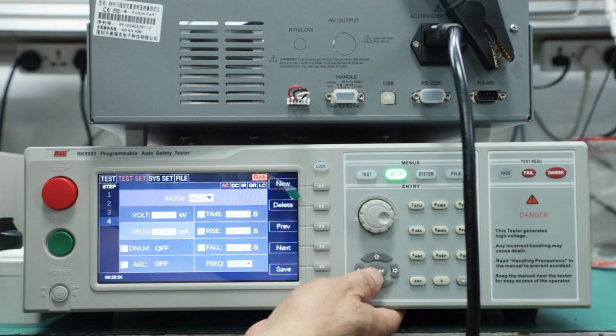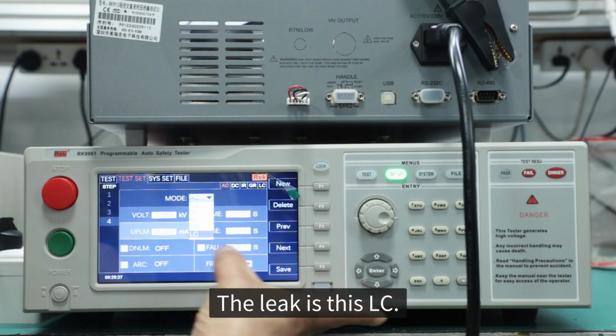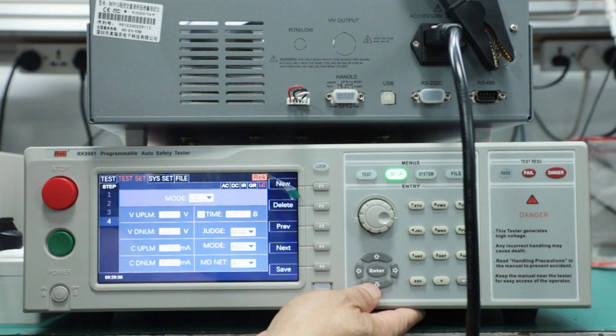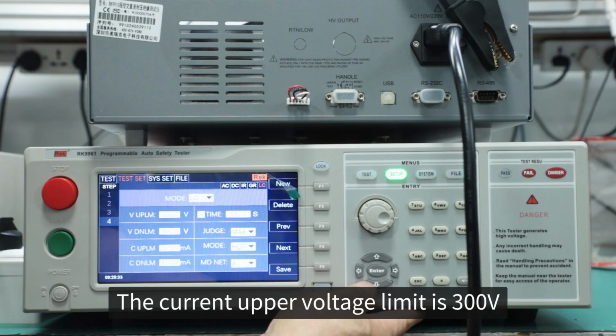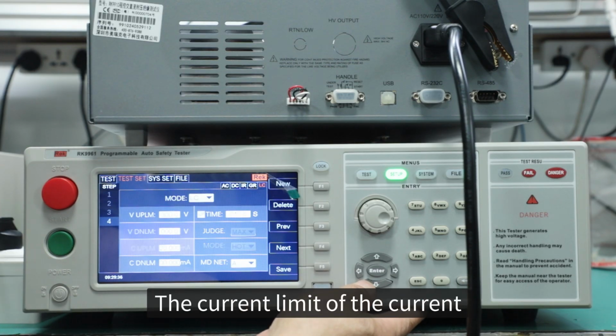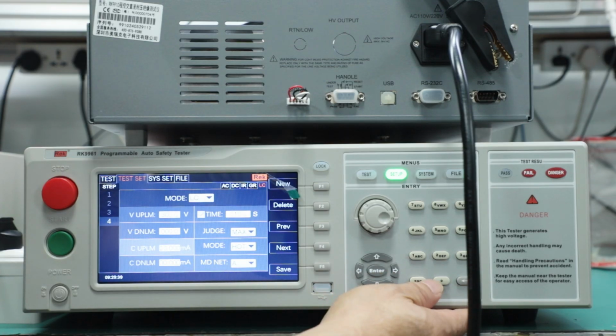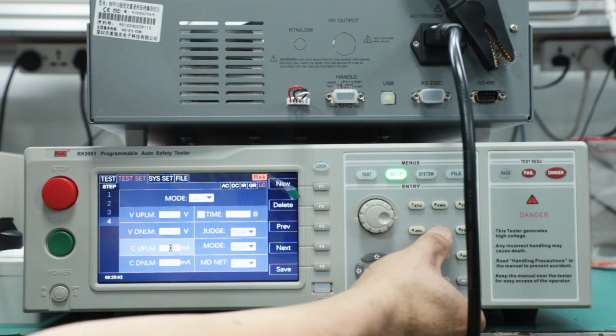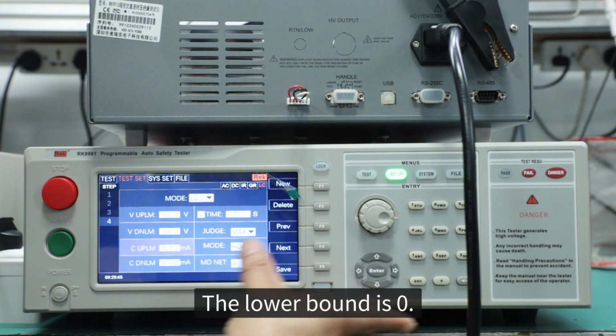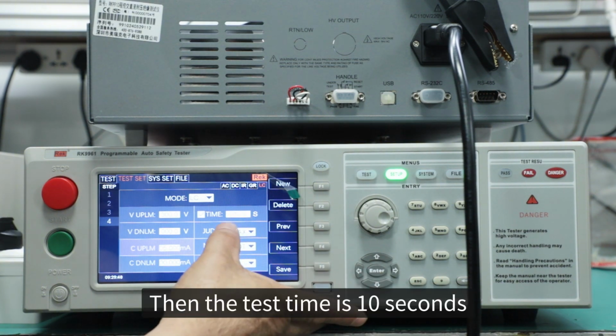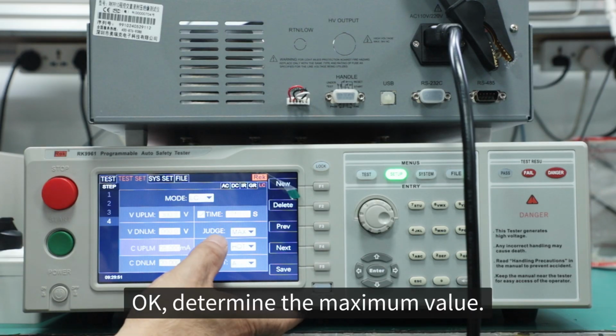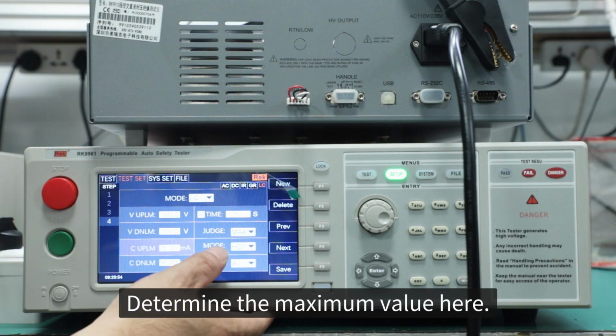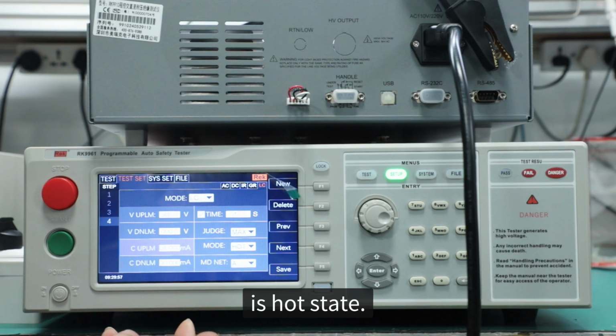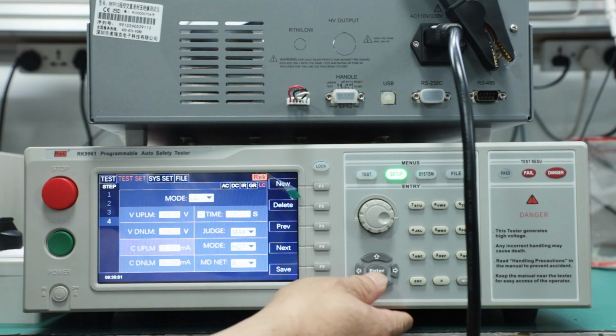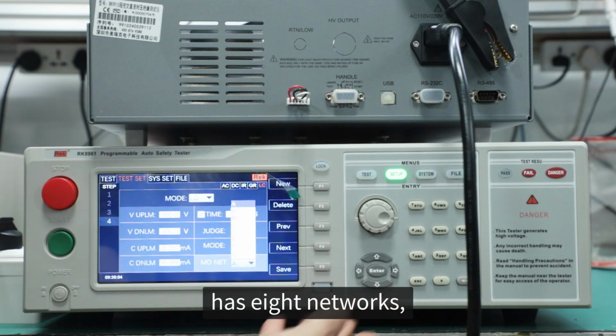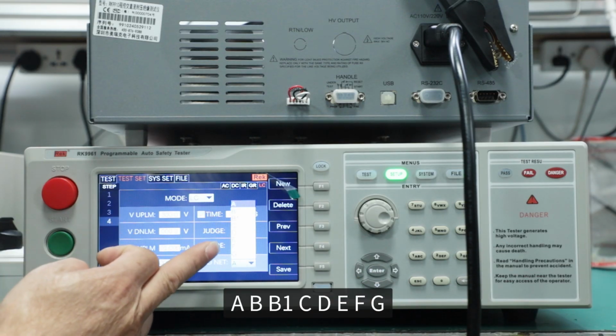Check for leakage. The leakage is this LC. The upper voltage limit is 300 volts. The lower limit is set to 0. The current limit is set to 5 milliamperes. The lower bound is 0. Then the test time is 10 seconds. Okay, determine the maximum value here. Test mode is hot state. MD network, select a network. It's this MD network. It has 8 networks: A, B, B1, C, D, E, F, G.